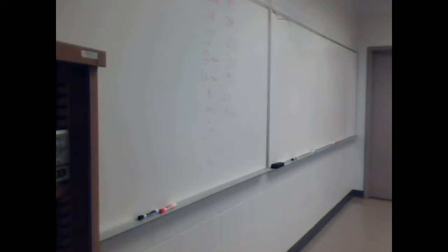I didn't get that written down. I think he said 7 amps per ton. Yeah, so 21 amps is what it should be. 3 times 7, the expected amps should be 21.